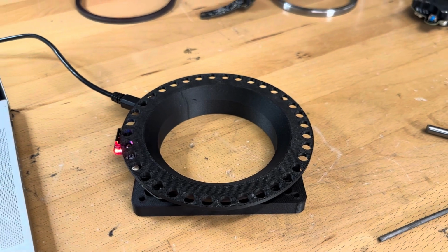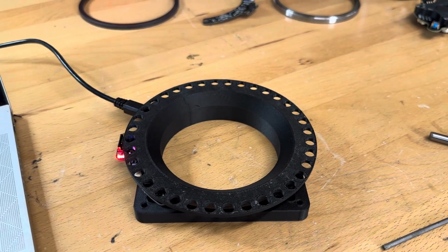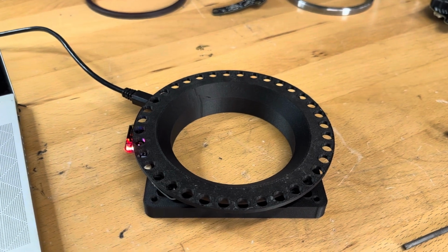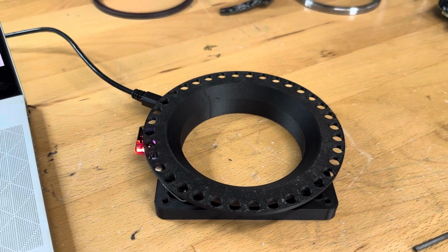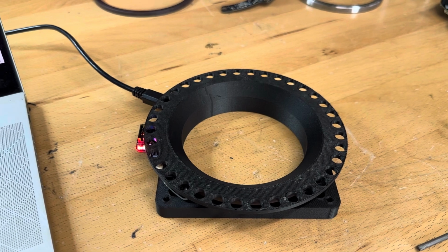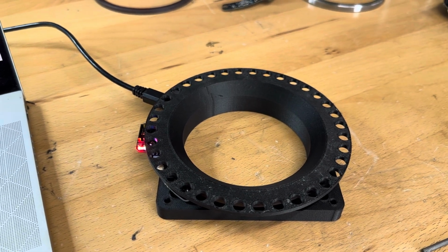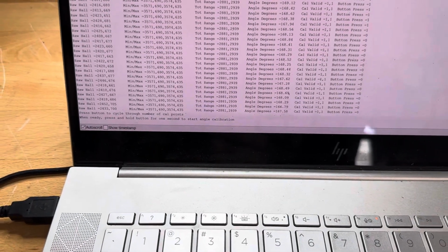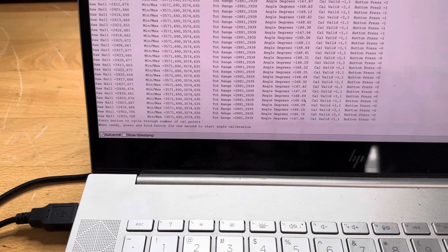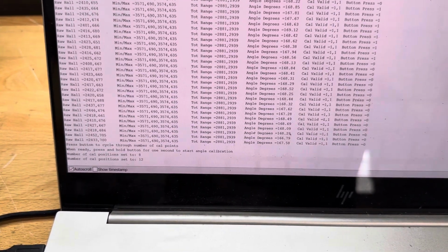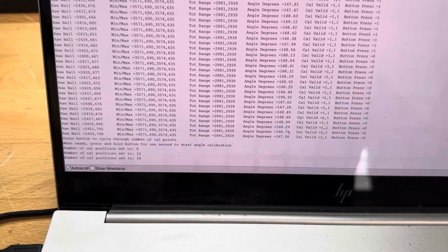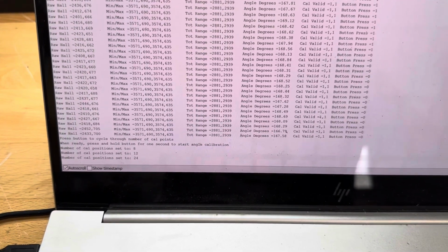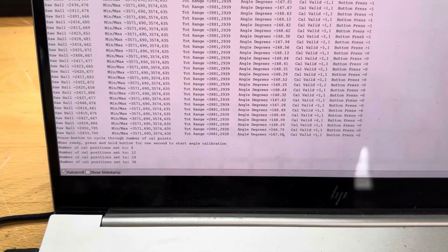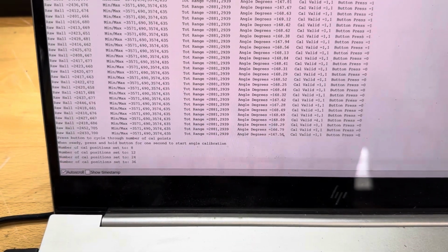resolution. Now this sensor at its best is good to about 1 degree of accuracy. So perfectly calibrated with the perfect air gap and everything, that's probably the best you're gonna hope for on a repeatability basis. But now that we're there, first thing a sensor needs us to do is choose a number of cal points. So pressing the button will cycle through them. You can get 8, 12, 24, or 36. I'm gonna go for 36 for this example. I'm gonna press and hold the button now to launch us into the advanced calibration.